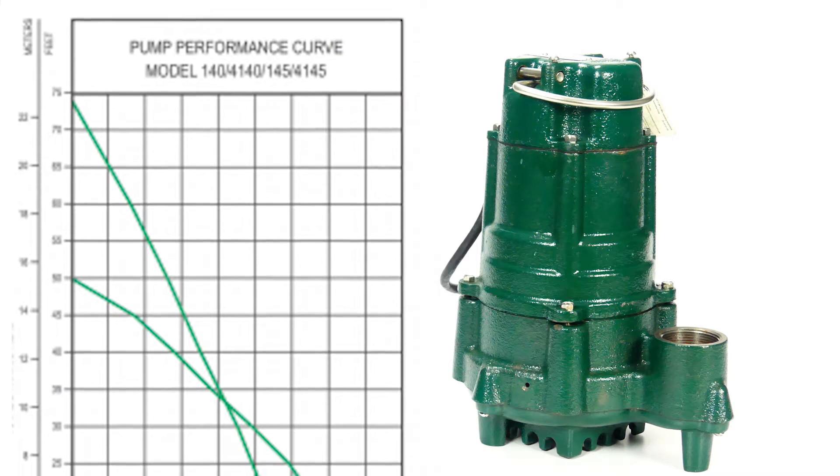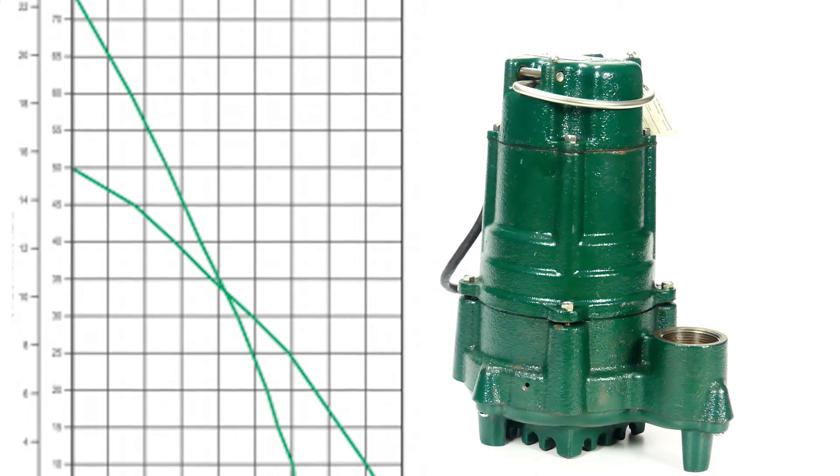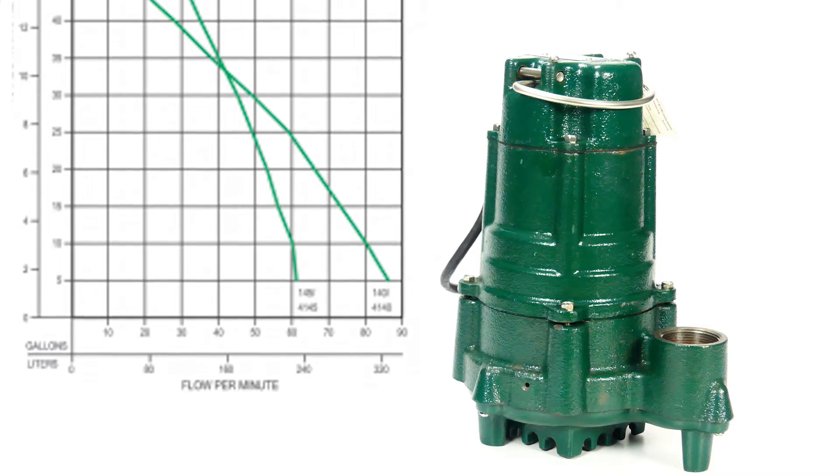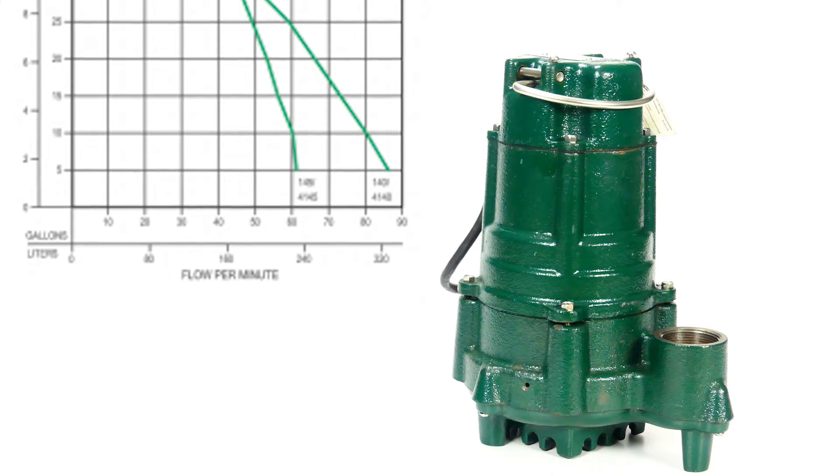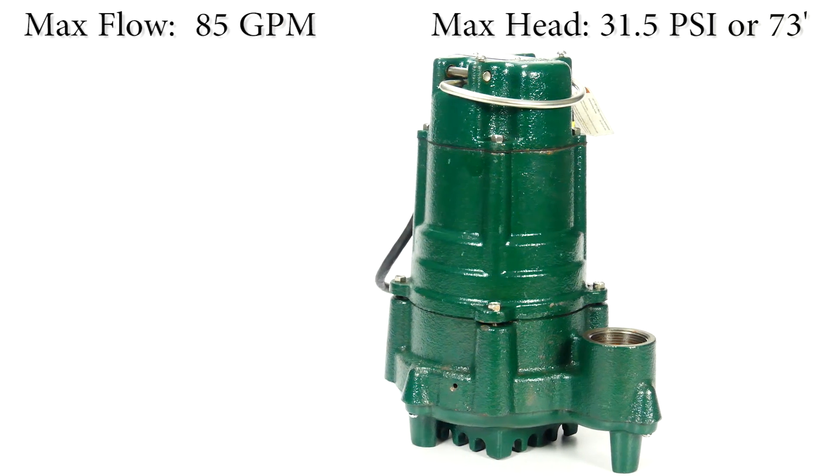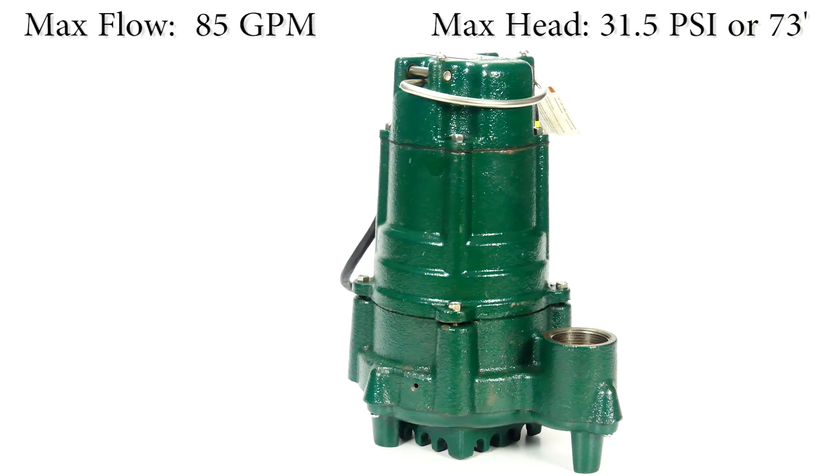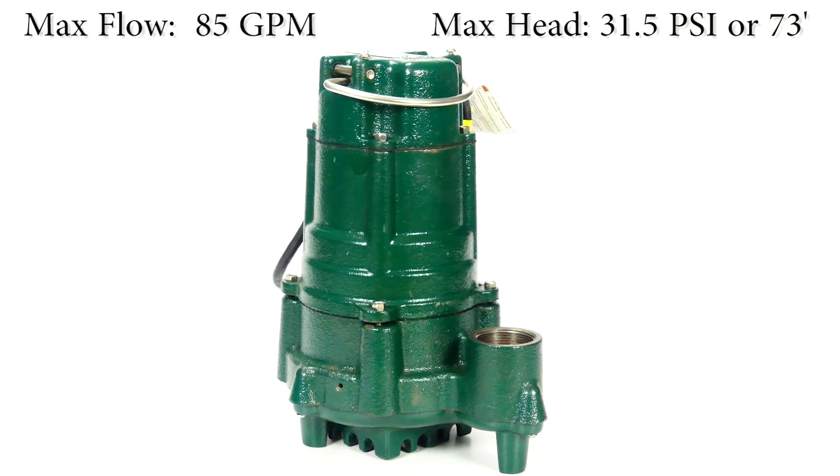This series is capable of producing a maximum flow rate of about 85 gallons per minute and has a shutoff pressure of approximately 31.5 psi or 73 head feet. As with every Zoeller pump, these are 100% pressure tested, submerged, and run before they leave the factory floor to ensure quality and reliability for years of trouble-free performance.